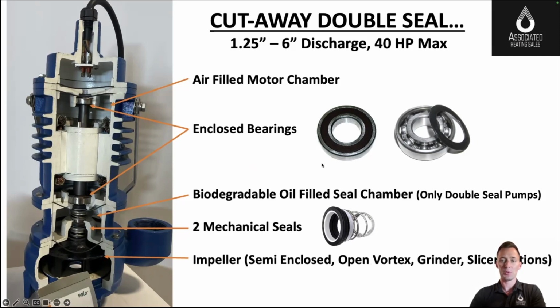They have fully enclosed bearings as opposed to open bearings where you're relying on that oil to lubricate the bearings. Oil may dissipate over time and leave those open, whereas Wilo has stuck with these fully enclosed bearings. So here's a cutaway. Wilo also sells single seal pumps.